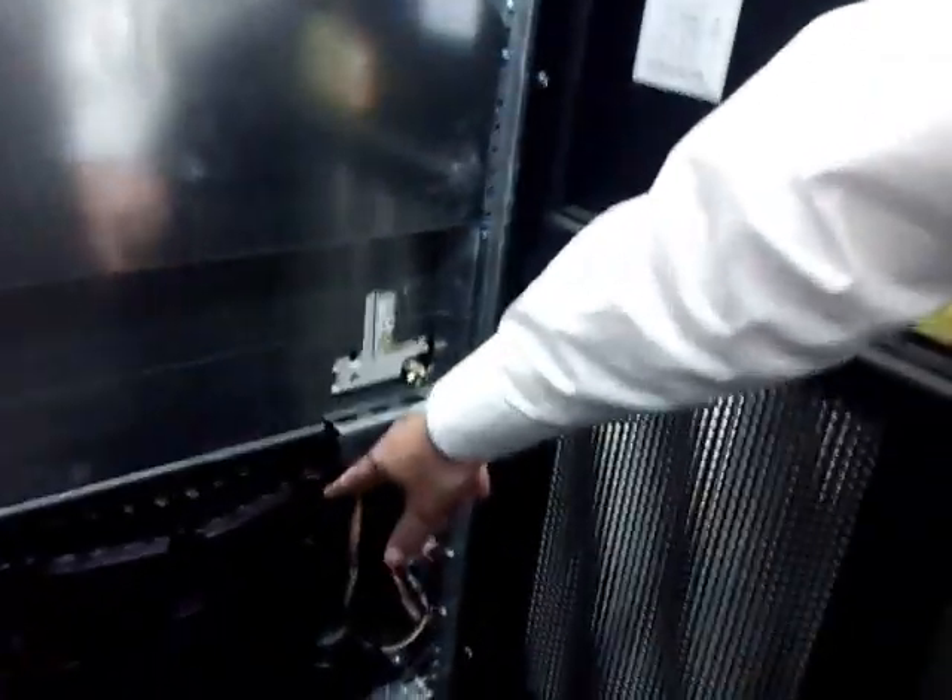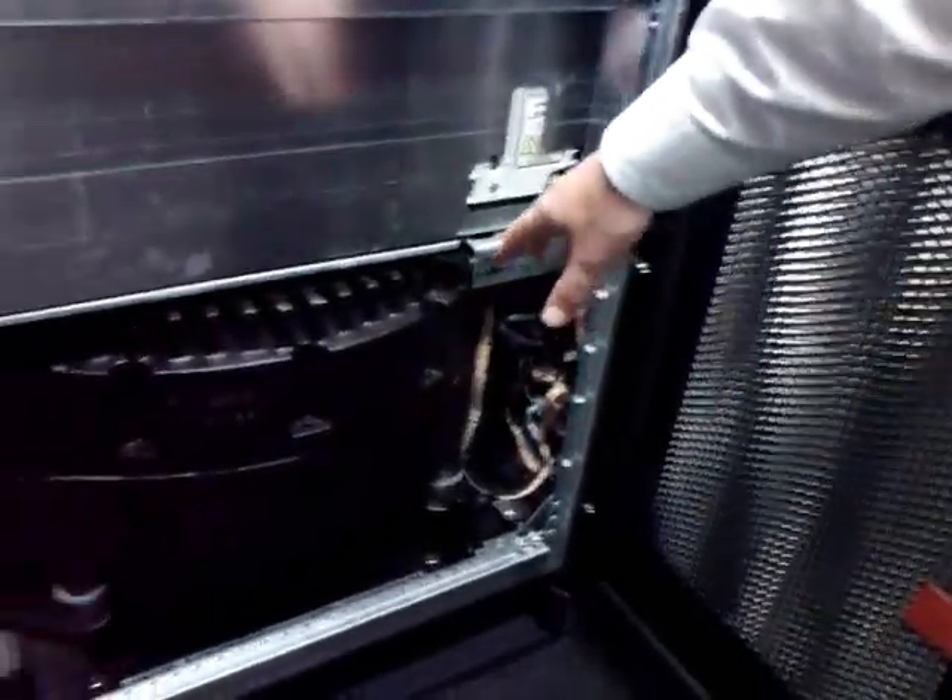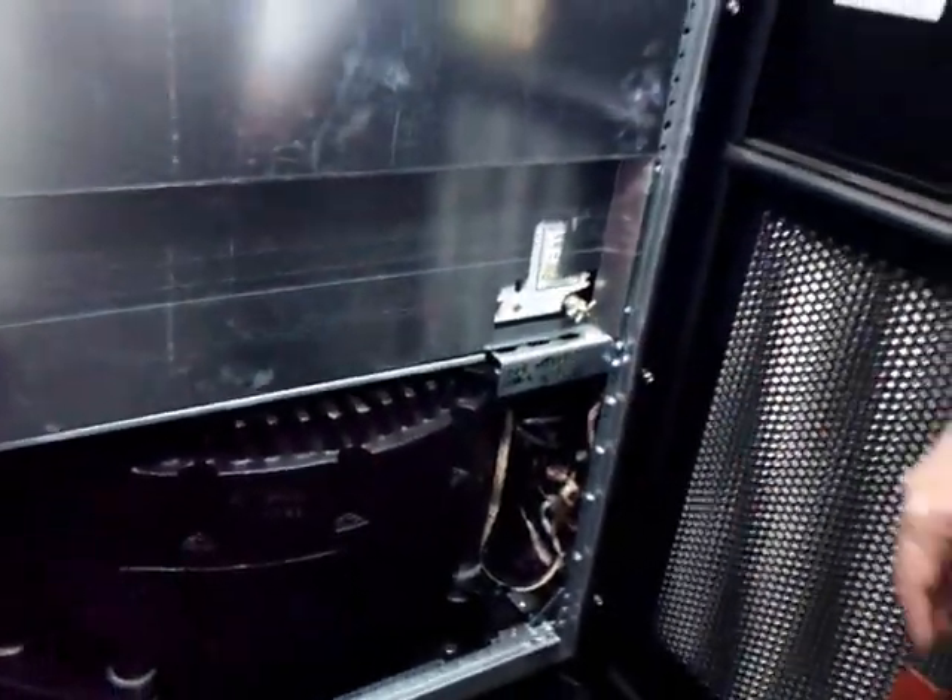Down here in the system, the flywheel provides 240 kilowatts of critical power in the unit. The unit you're looking at here is 150 kilowatts of UPS power — it's the smallest system we make. We make larger systems just by adding one of these cabinets to expand beyond that as well.